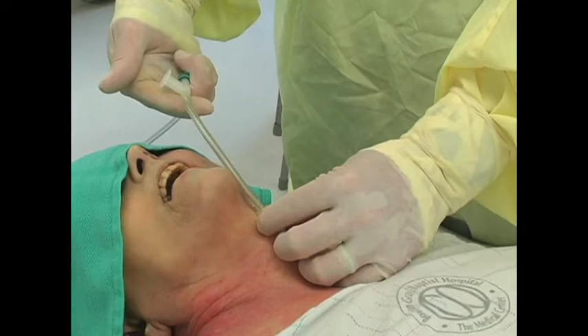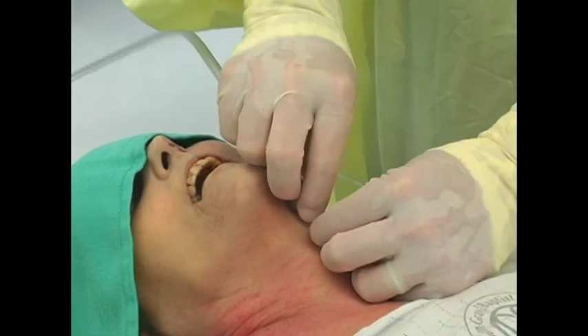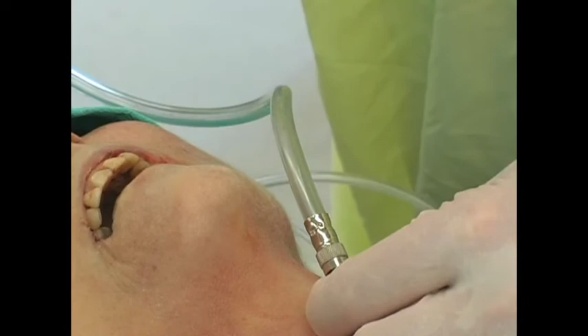Intermittent jet insufflation at 50 psi can be achieved by occluding the Y connector or side hole in the connecting tubing. Insufflate for 1 second and then release the occlusion for 4 seconds. To achieve the required high pressures, it is best to use a jet injector regulated by a flow meter attached to a wall unit or a tank. A regulated injector is preferred to an unregulated wall unit or tank.